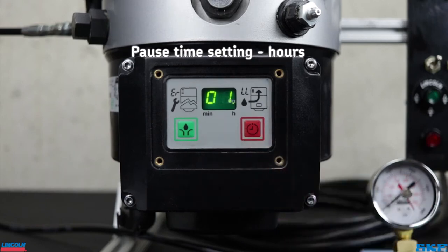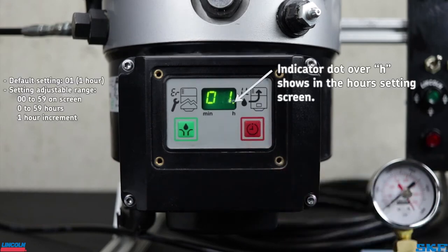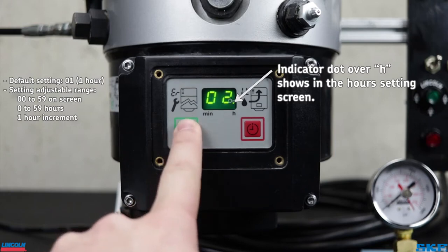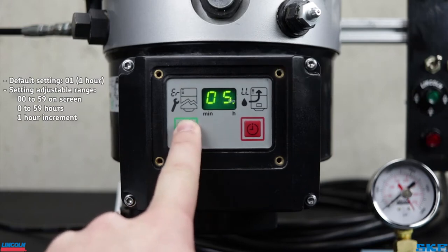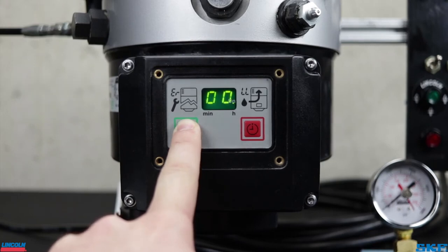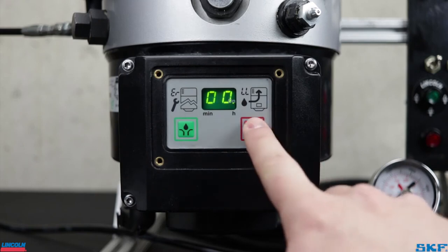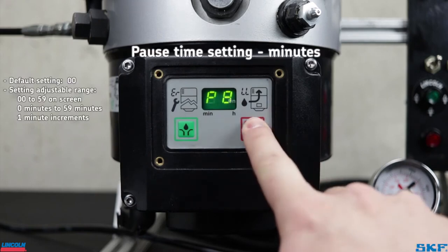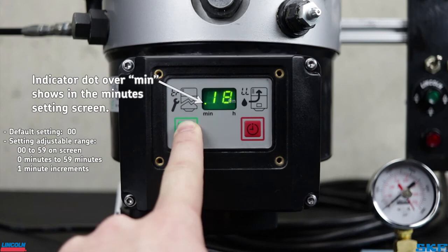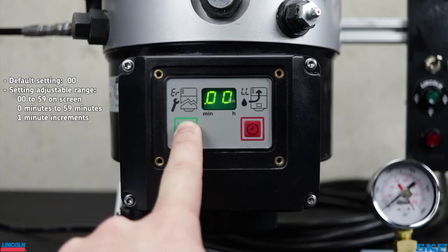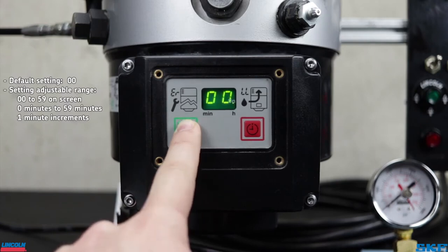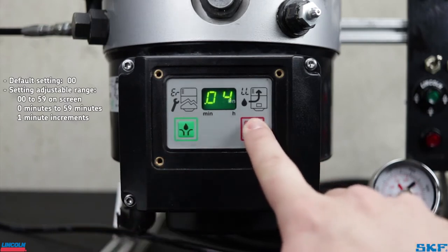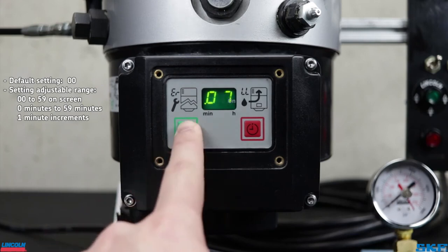This controls the hours pause time setting, which can be set from 0 to 59 hours. We can see here the unit is set to the factory setting of 1 hour. If you need to set the unit to run for less than 1 hour of pause, cycle through the values using the green button until you reach 0. Then cycle to the next programming screen by pressing the red button. P2 is the next screen which programs the minute's pause time. This can be set between 0 and 59 minutes when P1 is set to 1 hour or more. However, if hours on P1 is set to 0, the minimum pause time setting allowed is 4 minutes, but still can be programmed up to 59 minutes.